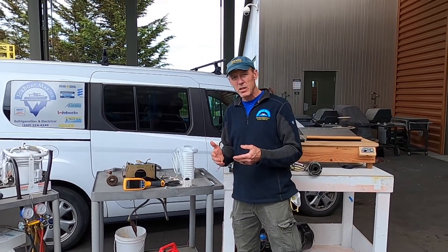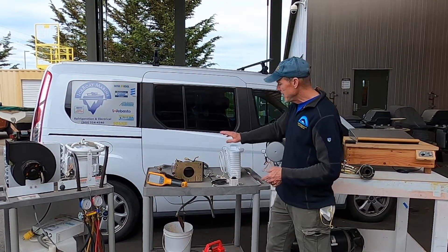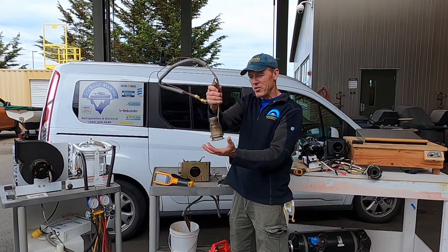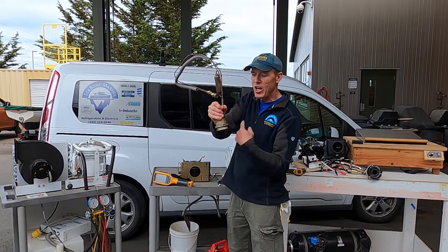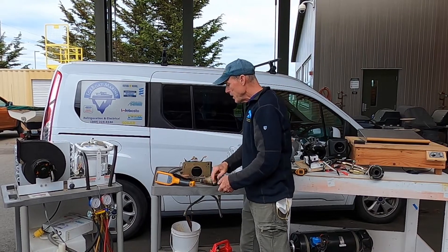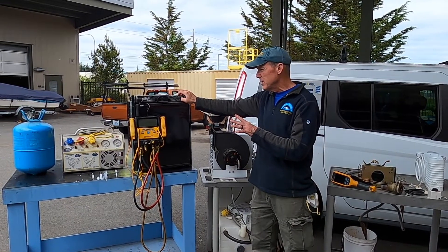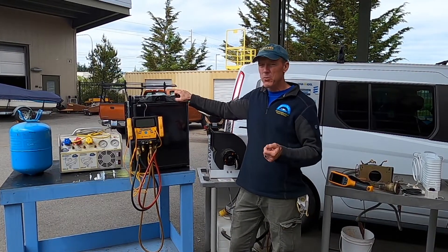When we're done with the heating part of the class, we move into refrigeration. Here's an example of a small system you might see on a sailboat: a small bin evaporator, a small compressor, and down below in the bucket is the actual thru-hull condenser. It goes under water thru-hull — the galley drain comes down through here, there are copper coils, and it turns the refrigerant back to a liquid. It's perfect for small boat refrigeration needs. We have lots of other types of refrigeration on board, from big to small, and we even have some boxed-type refrigerators. The focus is not so much on installing them — an owner can do that — but more the troubleshooting and the theory behind how they work.